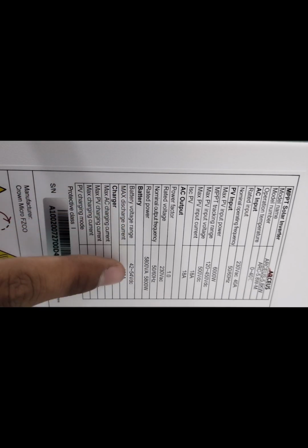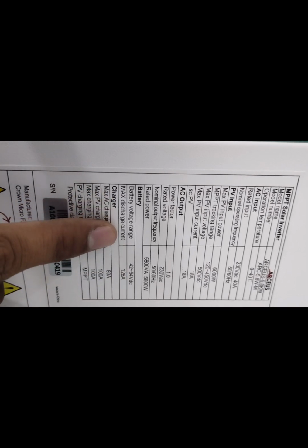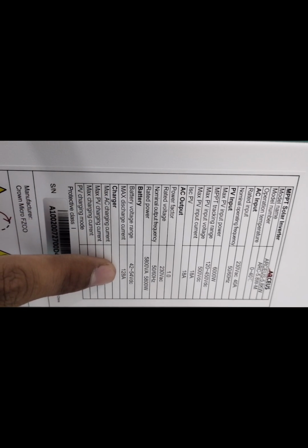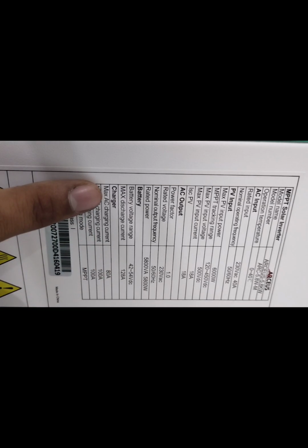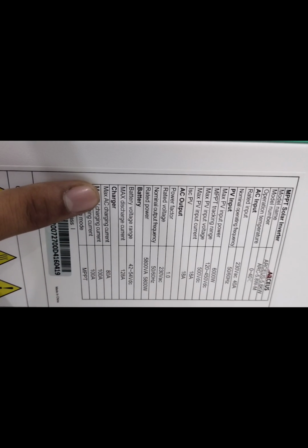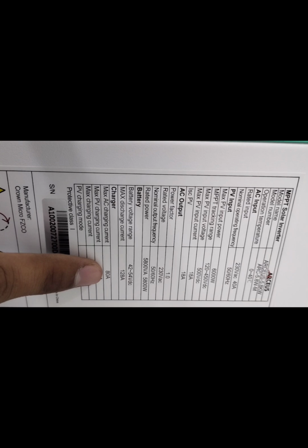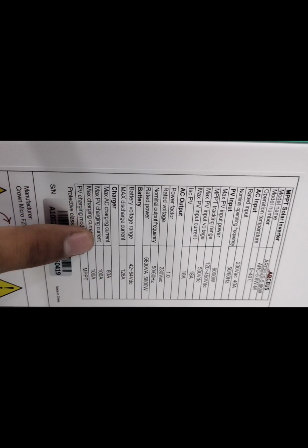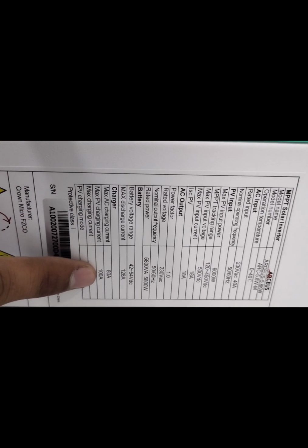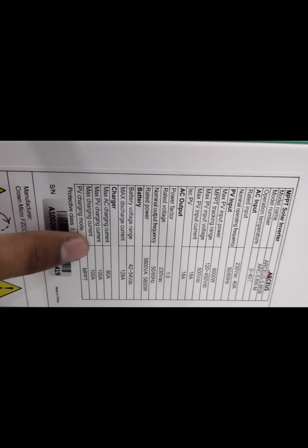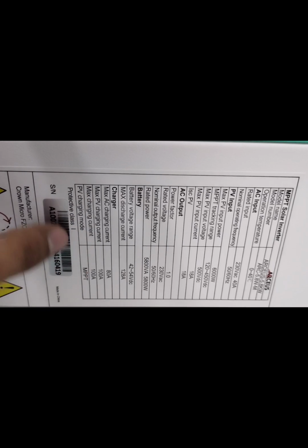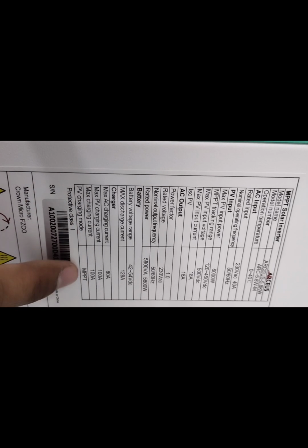Battery voltage range is 42 to 54 volt DC. Maximum discharging current it supports is 128 ampere. Then we have charging data. Maximum AC charging current is 80 ampere. Maximum PV charging current it supports is 100 ampere. Maximum charging current is 100 ampere and PV charging mode is MPPT.